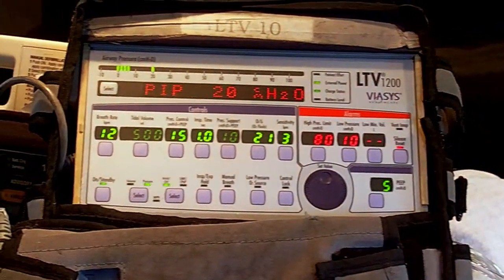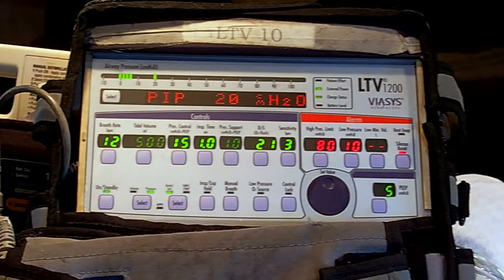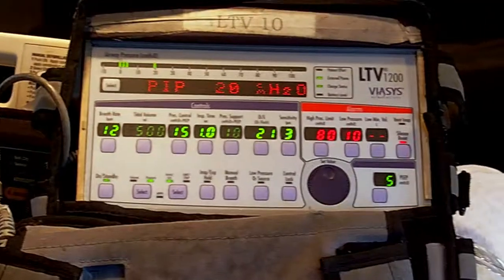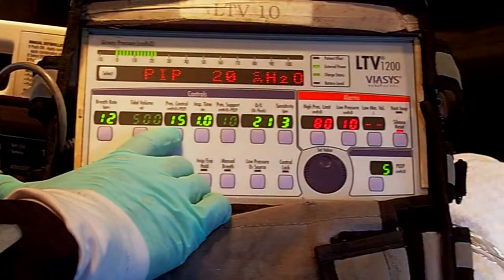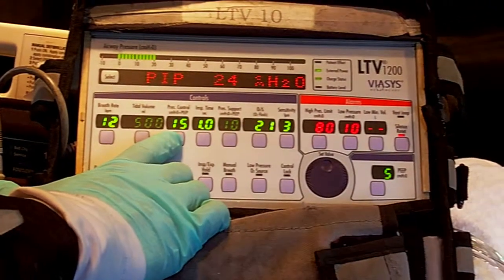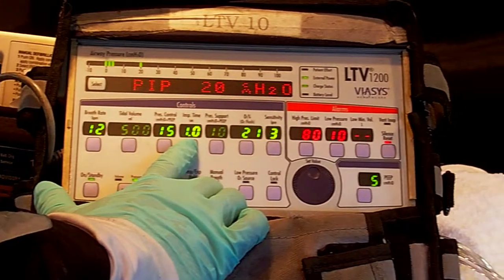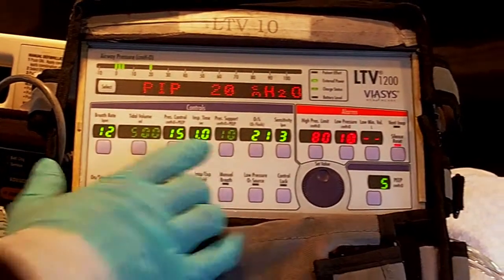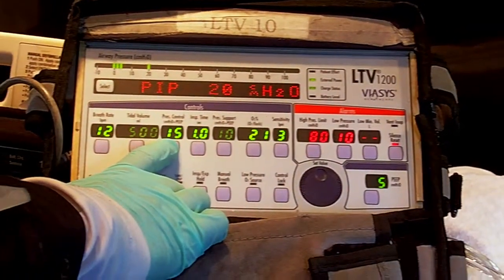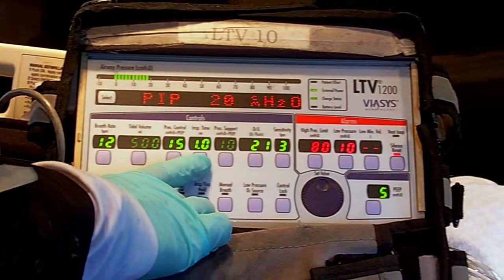Following that, we have pressure assist. 'Assist' means the patient is drawing in to trigger with negative inspiratory force. Target is going to be 15 centimeters of water pressure. The cycle to turn off is going to be the inspiratory time — one second. To recap: pressure assist — trigger is patient effort, target is 15 centimeters of water pressure, and cycle is one second.